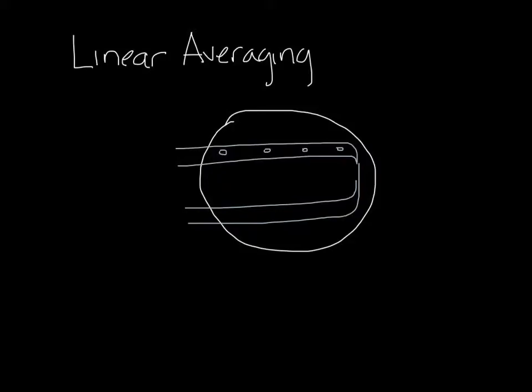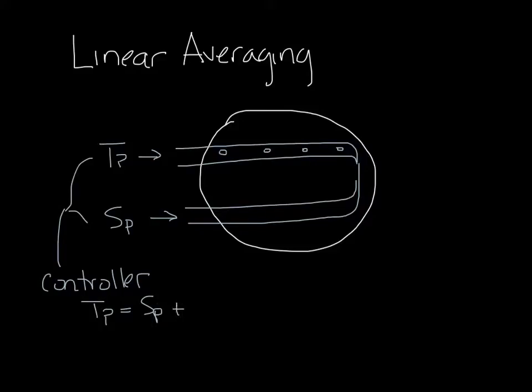So if you're looking into this flow sensor and the airflow is going in the direction you're looking, the top one would be measuring total pressure and the bottom one would be measuring static pressure. And then both of these are connected back to a controller. And if you remember, total pressure is static pressure plus velocity pressure. So the controller can use this information from the flow sensor to calculate velocity pressure, and therefore velocity, and therefore CFM.